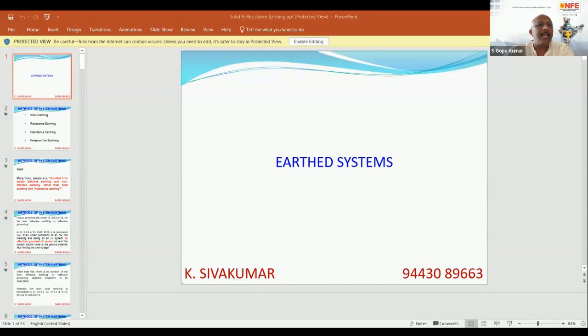Sir, shall I take the second question from the top? Yes, sir. There is a 3.3 kV by 415 volt transformer. The secondary is NGR grounded. Output voltage measurement shows a discrepancy in phase to earth voltage, while bypassing the NGR, the voltage between phase to earth is balanced. What could be the reason? First of all, a 415 volt transformer neutral is not supposed to be NGR grounded.